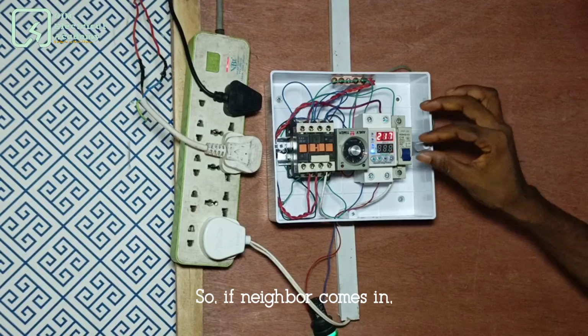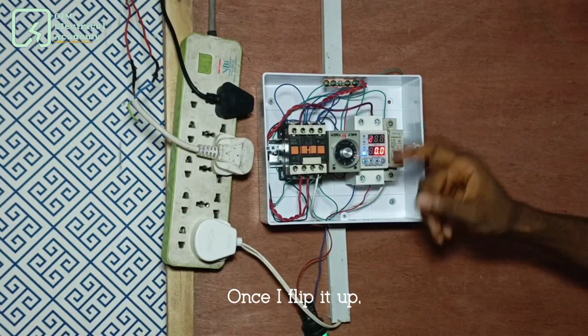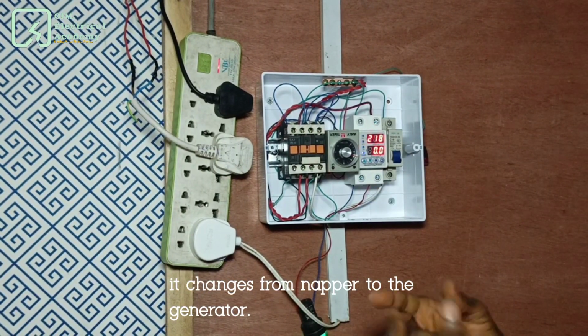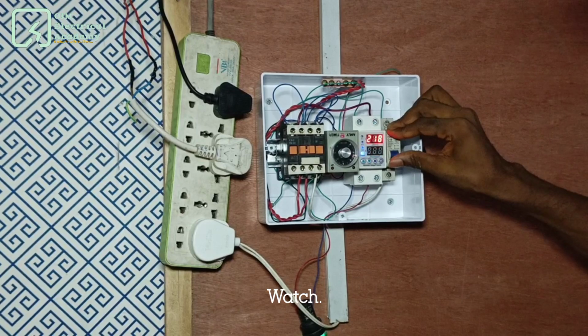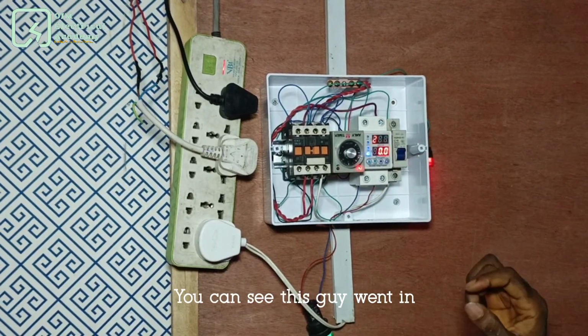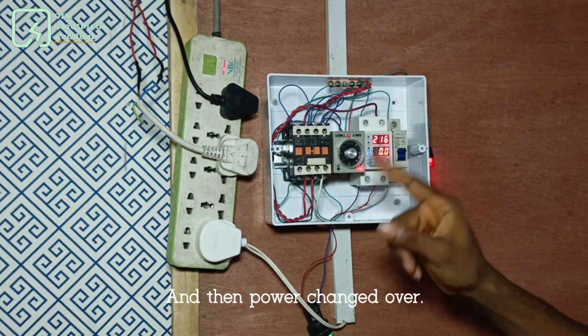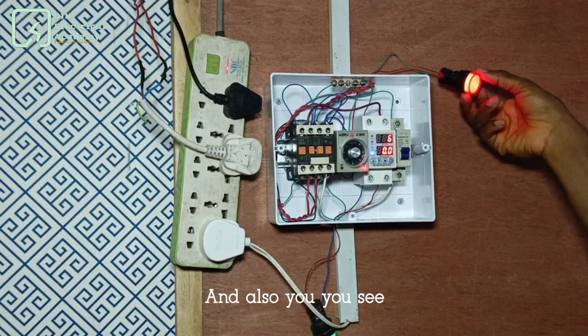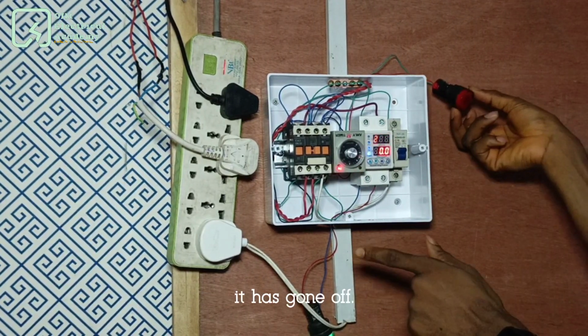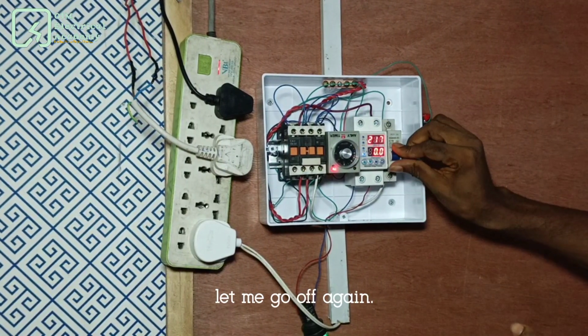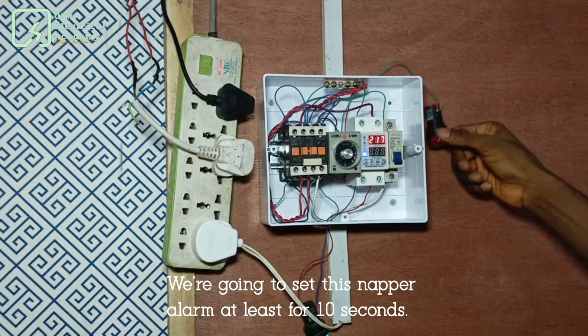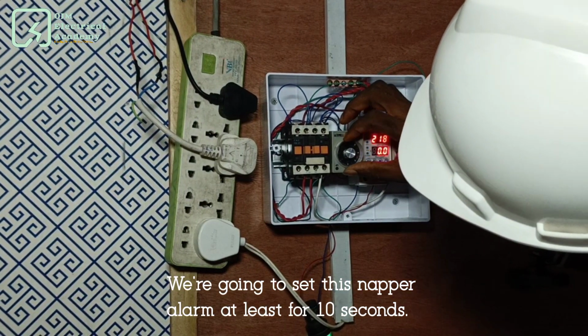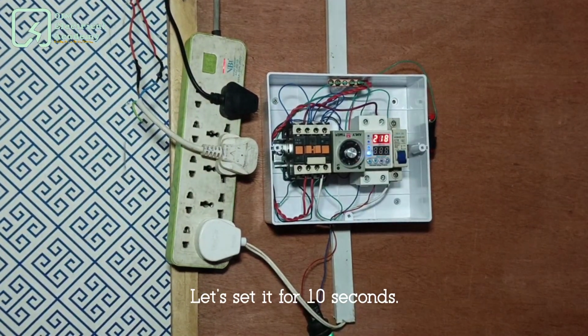So if NEPA comes in, this is our NEPA breaker. Once I flip it up, it changes from the generator to NEPA. Watch. You can see this went in when I pressed it on, and then power changed over. And also you see that this one, which is our NEPA alarm, has gone off. Let me go off again. We are going to set this NEPA alarm for at least 10 seconds. Let's set it for 10 seconds.